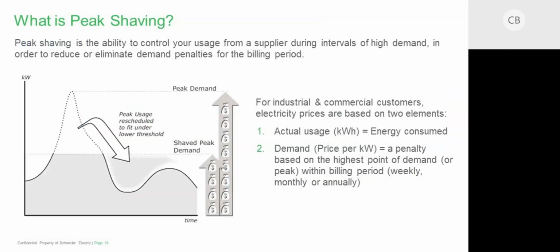So what is peak shaving? We talked about that. Here you'll see this is an illustration on the left of a load graph. And in the morning, or in the evening hours, you may be low load. You don't have a solar load on the building. And in the afternoon, buildings will heat up, the cooling load will increase, and you'll see a peak demand. Now, in data center worlds, we don't see as great of a change in the load profile as we do in a commercial office building. A commercial office building is empty at night, and in the day, starting at 6, 7 in the morning, people start to funnel in, and then the sun comes up and starts beating down on it, and you'll see a dramatic rise from the evening hours to the peak daylight hours.